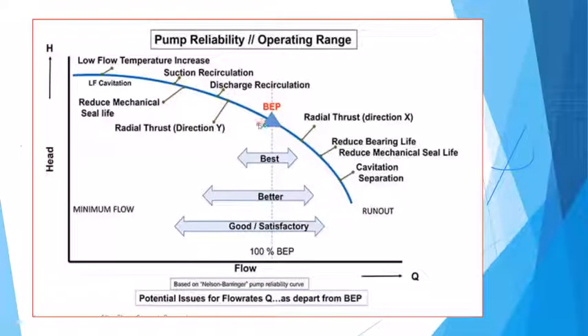And so when you're starting and stopping a motor, and it gets important when you're buying and putting equipment in, it's important that we talk to the pump people about where the best efficiency point is, period. So we know. The issue you also have to look at is there are different design types of pumps, but we want to find out from them what's the best speed, what's the best point, and then design everything to that point. So if you're running it at 1800 RPM, or you're running it at 3600 RPM, depending on the impeller size, where is that good point?